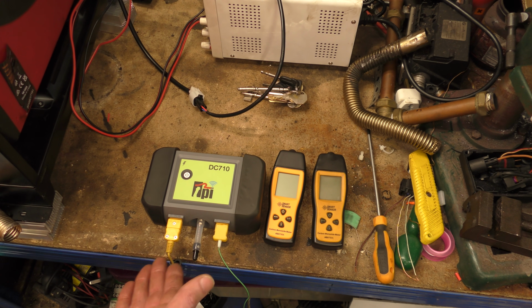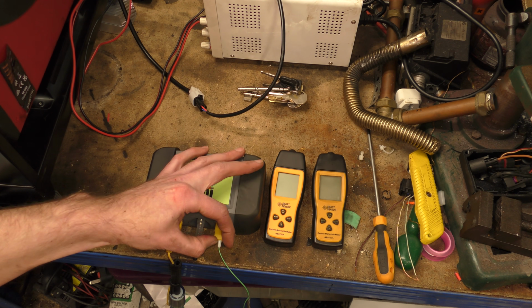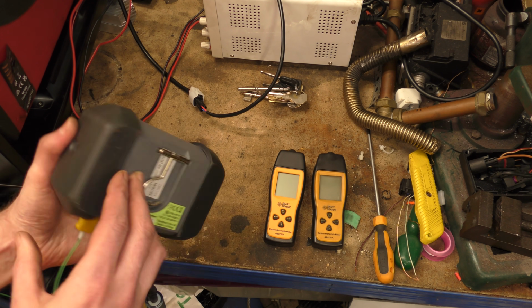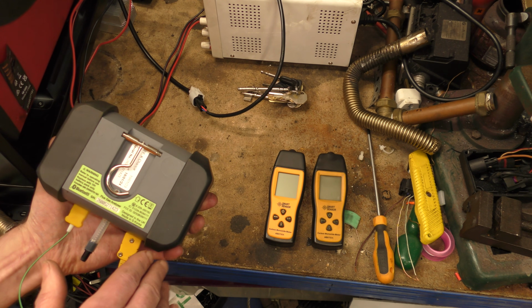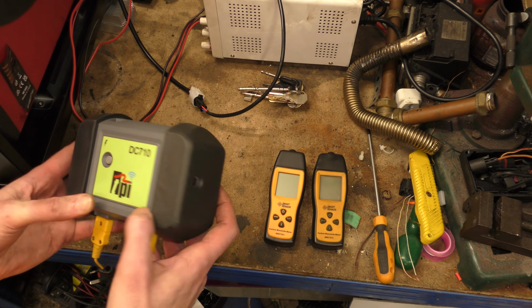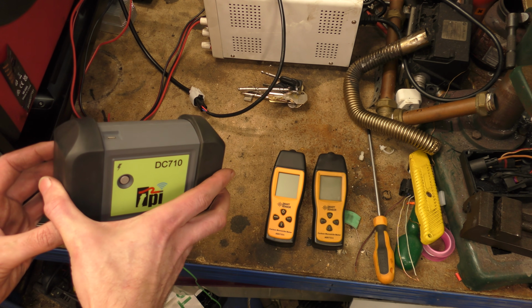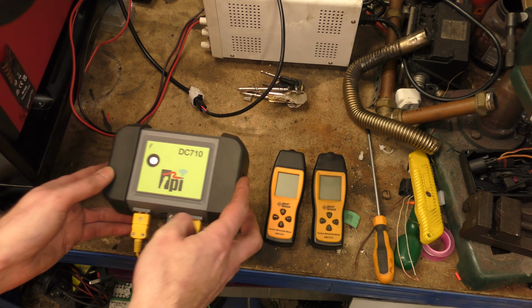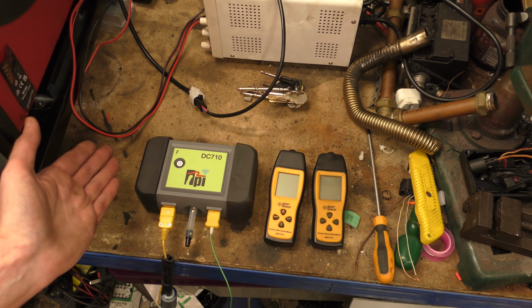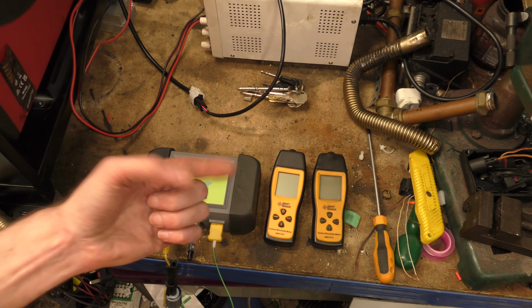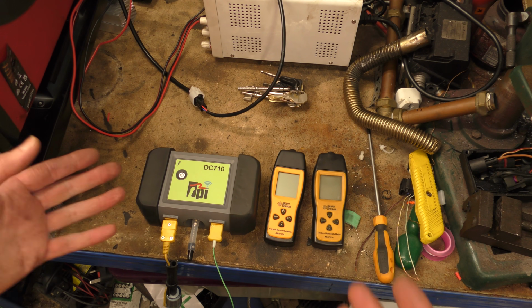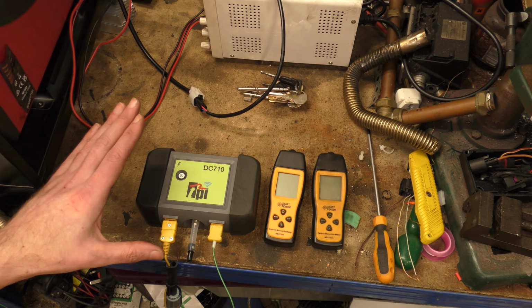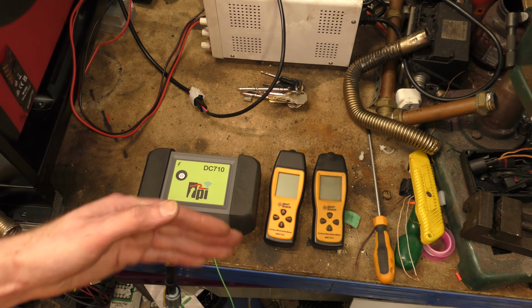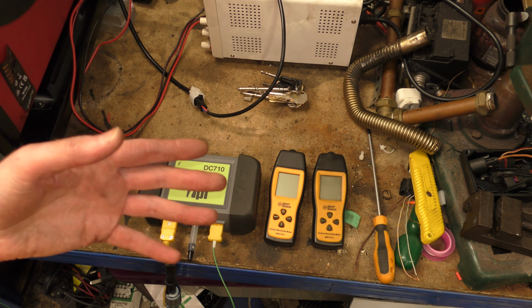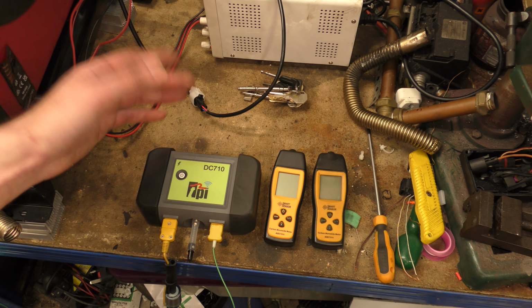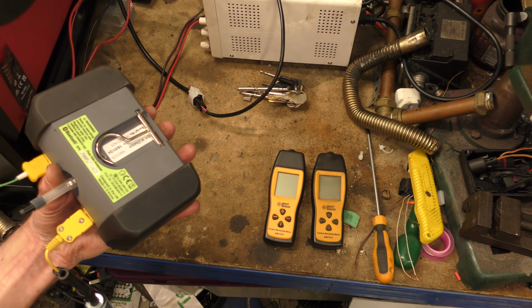basically, as I say, it's a stick with a hose in the end of it. There's nothing high-tech about that, and a temperature probe. There's nothing exciting about that. But this is a really nice thing. It's so nice. It's got a hook, which is nice, but it's also got giant magnets in it, so you can stick it to, well, it would be the side of your gas boiler. But had the cover been on this diesel heater, we could have stuck it to the side of the diesel heater. But for us, it's ideal that we can record the actual data on our phones, so we can have this camera pointed at everything and still be able to capture the data that we need from the heater output. So we're going to be using that more for testing of outputs and carbon monoxide, carbon dioxide, and testing efficiency of diesel heaters and other things, and just playing with it in general, because I like to play with things like that. It is very cool.